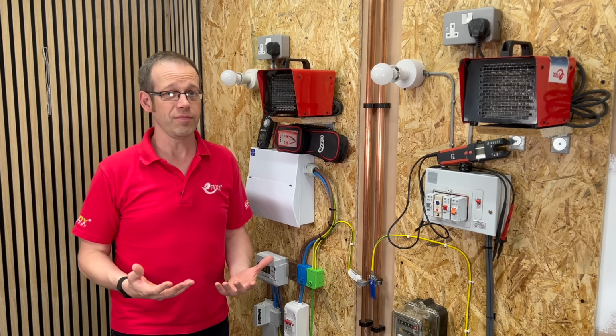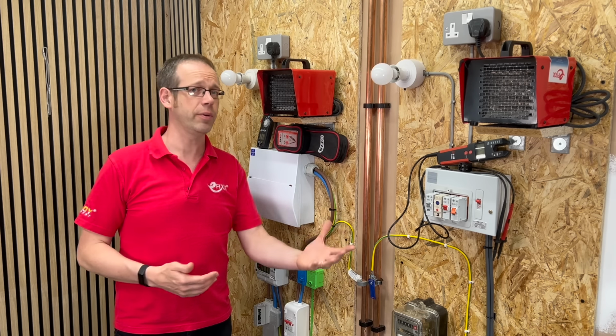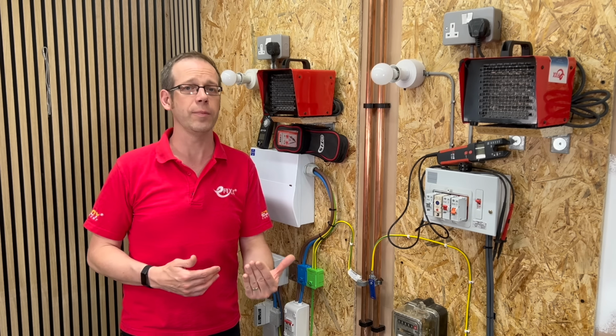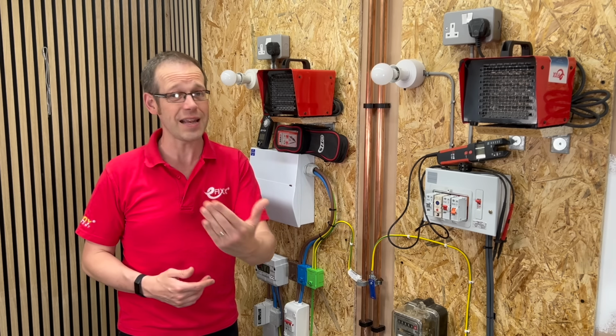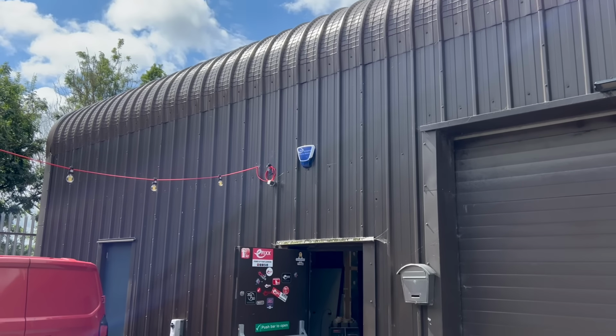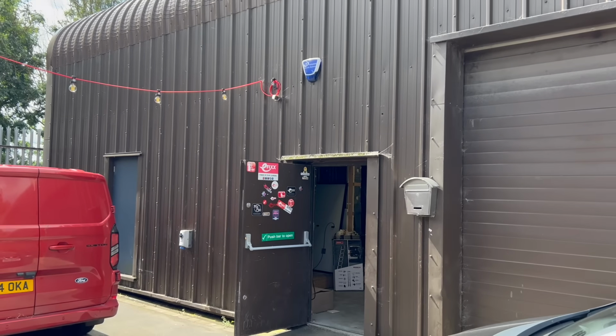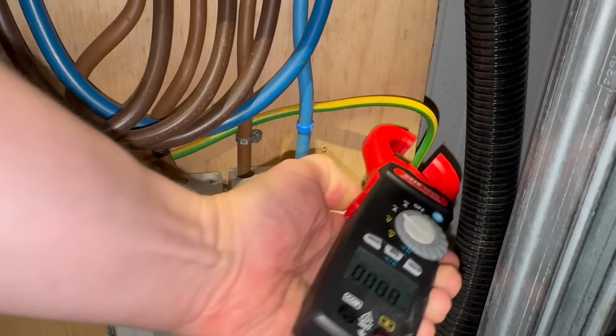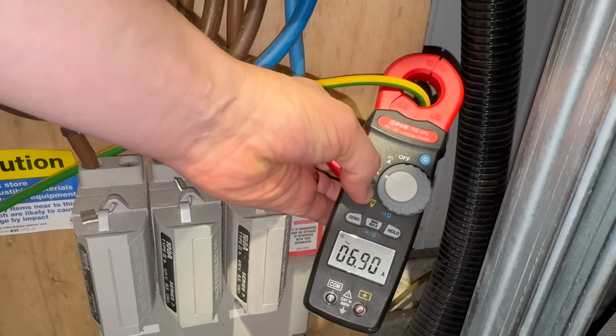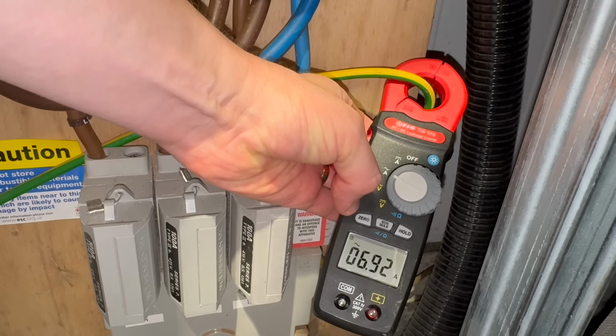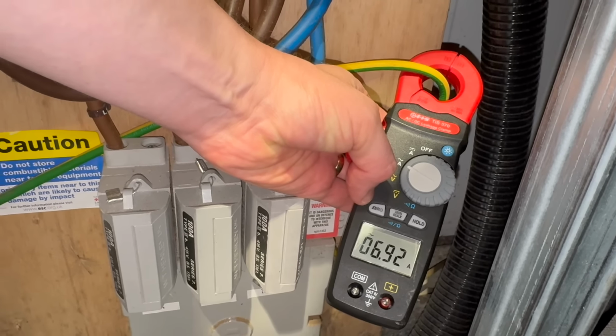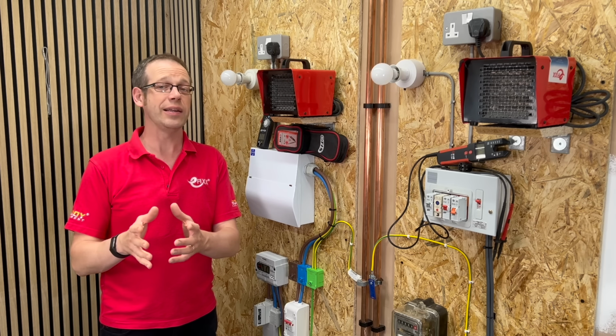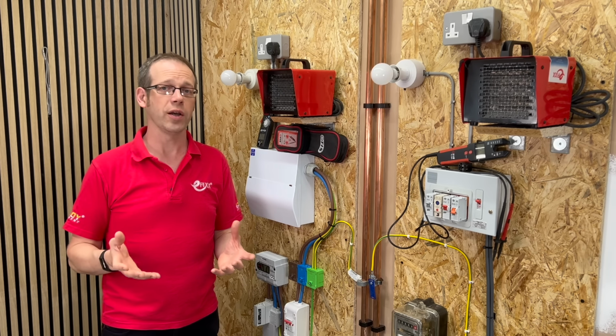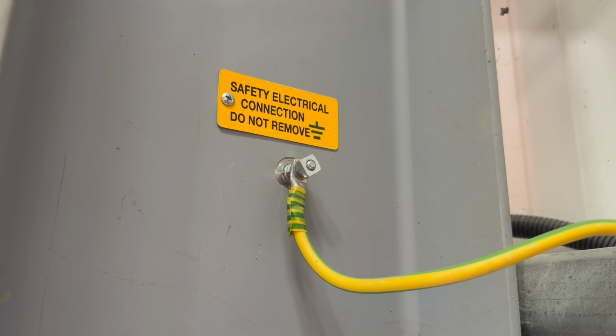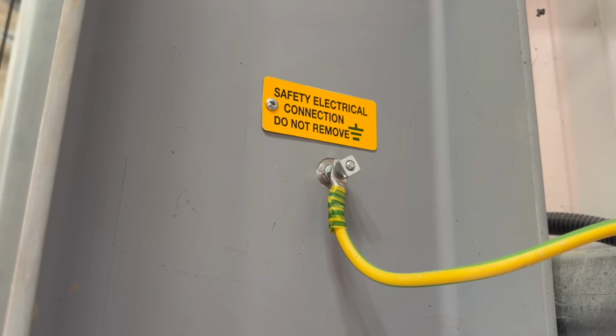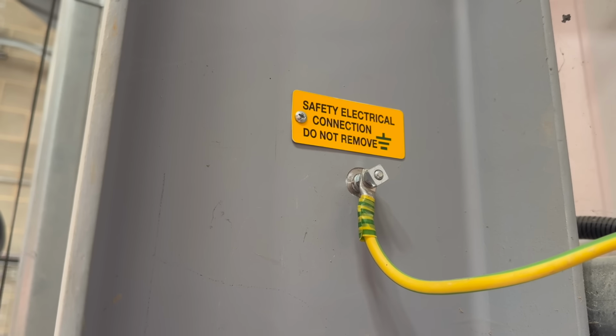Indeed, in a healthy system, it doesn't actually matter. That current flowing through your earthing system and even through the water pipe doesn't cause any harm or even potential harm. In fact, we can demonstrate this in our industrial unit cum recording studio here. If we pop a clamp meter around our main earthing conductor here, we can see that there's a reasonably sized amount of current flowing through here. Now, this might lead you to think that there's a serious problem here, as we've outlined already in our demo rig, but actually, this is just the way a TNCS system works when you've got common metalwork between buildings. Here, it's as likely to be the bonded structural steel as much as the water pipes that's creating all the extra routes for the current.